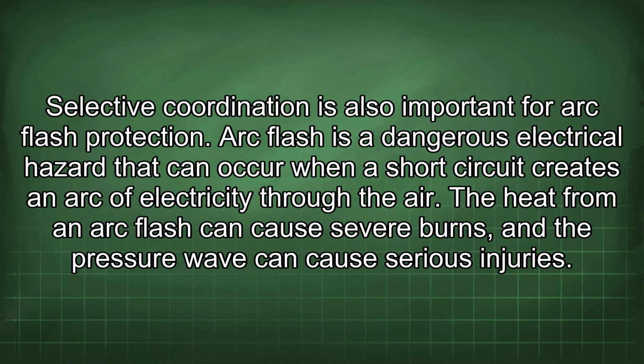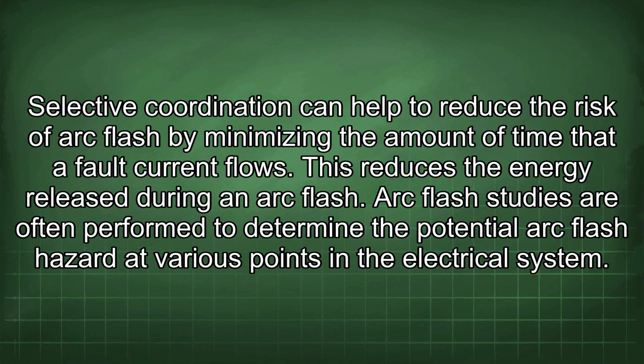Selective coordination is also important for arc flash protection. Arc flash is a dangerous electrical hazard that can occur when a short circuit creates an arc of electricity through the air. The heat from an arc flash can cause severe burns, and the pressure wave can cause serious injuries. Selective coordination can help to reduce the risk of arc flash by minimizing the amount of time that a fault current flows. This reduces the energy released during an arc flash.